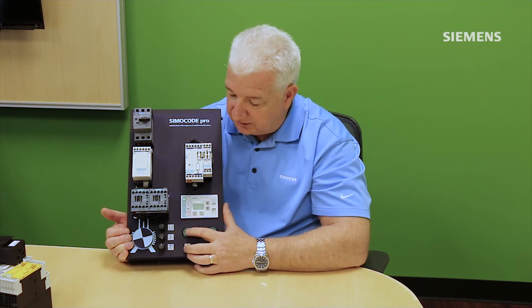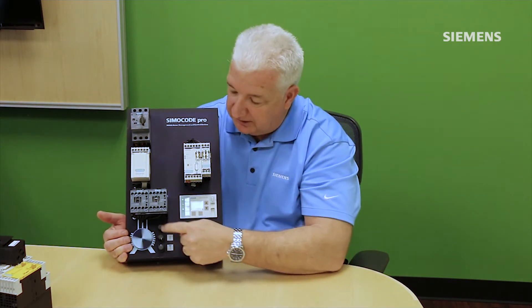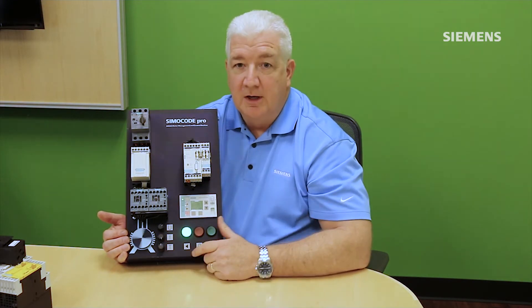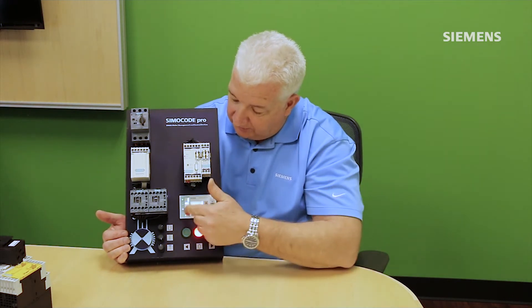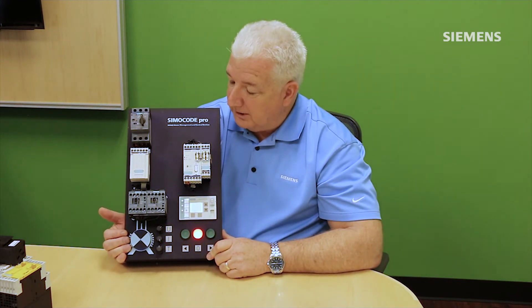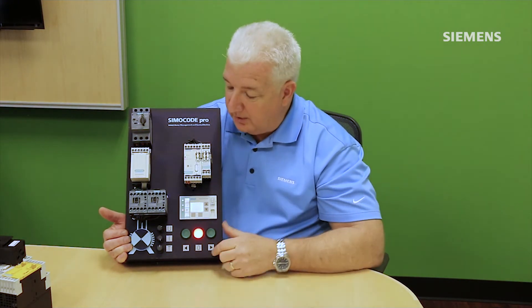This demo comes pre-programmed to showcase these features. The knobs allow adjustment of voltage and motor current simulation. I've turned up the current knob to induce an overload condition. SIMOCODE can also monitor a built-in thermistor. Here I've generated an overload condition, and you can see a flashing red light on the SIMOCODE and also on the optional operator panel to annunciate the fault. Pressing the local blue reset button — or an HMI button — acknowledges the fault and the red light goes solid.